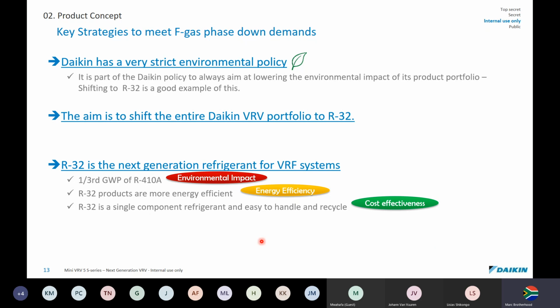Further to that, R32 is a single component refrigerant. Conventionally, R410A is a blend of R125 as well as R32. If you have major leaks, you cannot just top up with R410A because you don't know what's leaked more. Is R125 leaked out more, or is R32 leaked out more? The advantage here is very similar to R22: if there's a leak, you don't need to recover all the refrigerant. You can just top up because it is a single component refrigerant. It's not a blend.